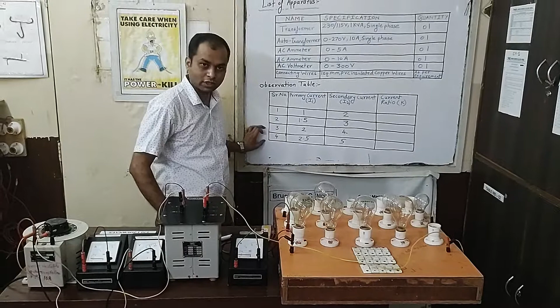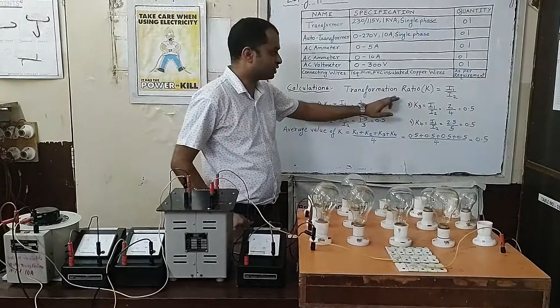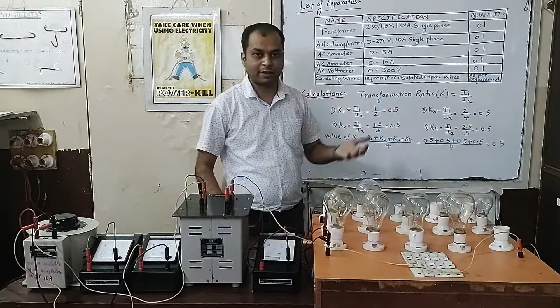Now let us have a look at the calculation part, how to calculate the current ratio K. In the calculation part we have to calculate the transformation ratio K using the formula I1 by I2, that is, primary winding current to secondary winding current, for each and every reading. For the first reading, K1 equals I1 by I2, which is 1 by 2, giving 0.5. In the same way for the second reading, I1 by I2 is 1.5 divided by 3, which again gives 0.5. We do the same calculation for the third and fourth readings.